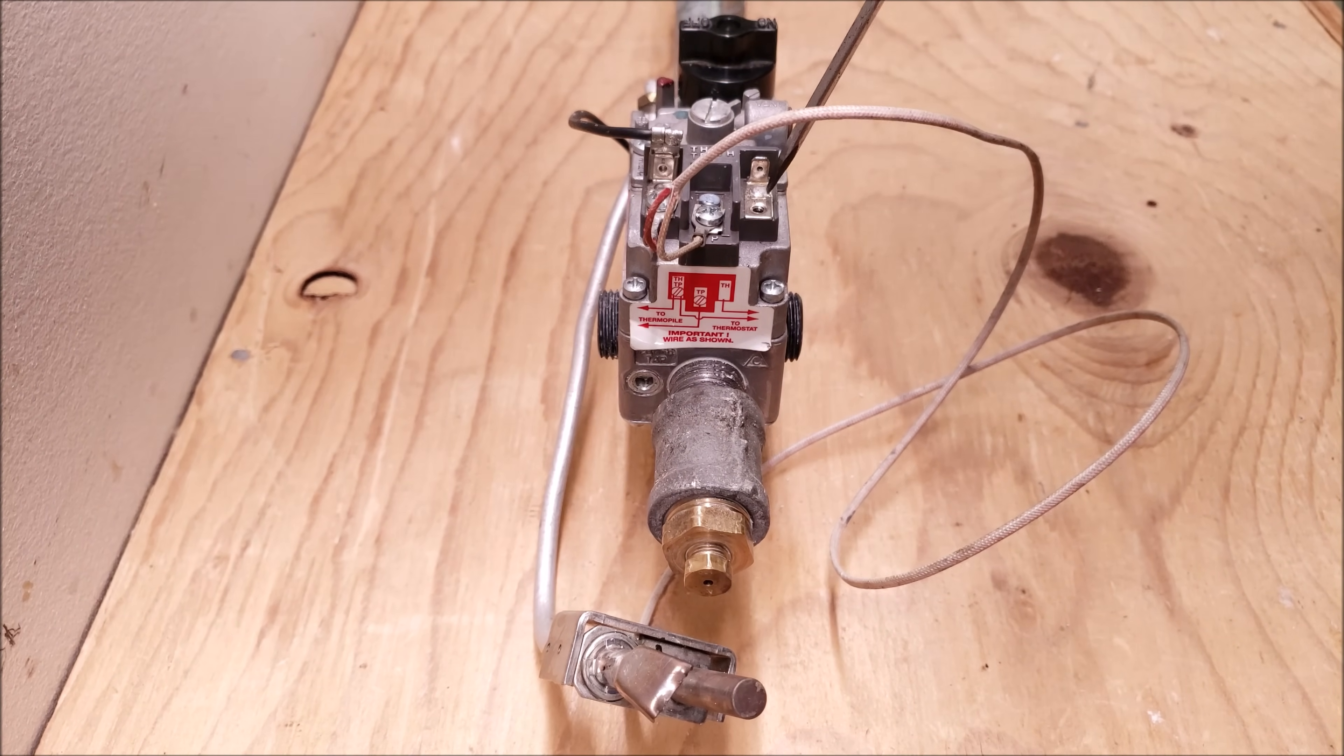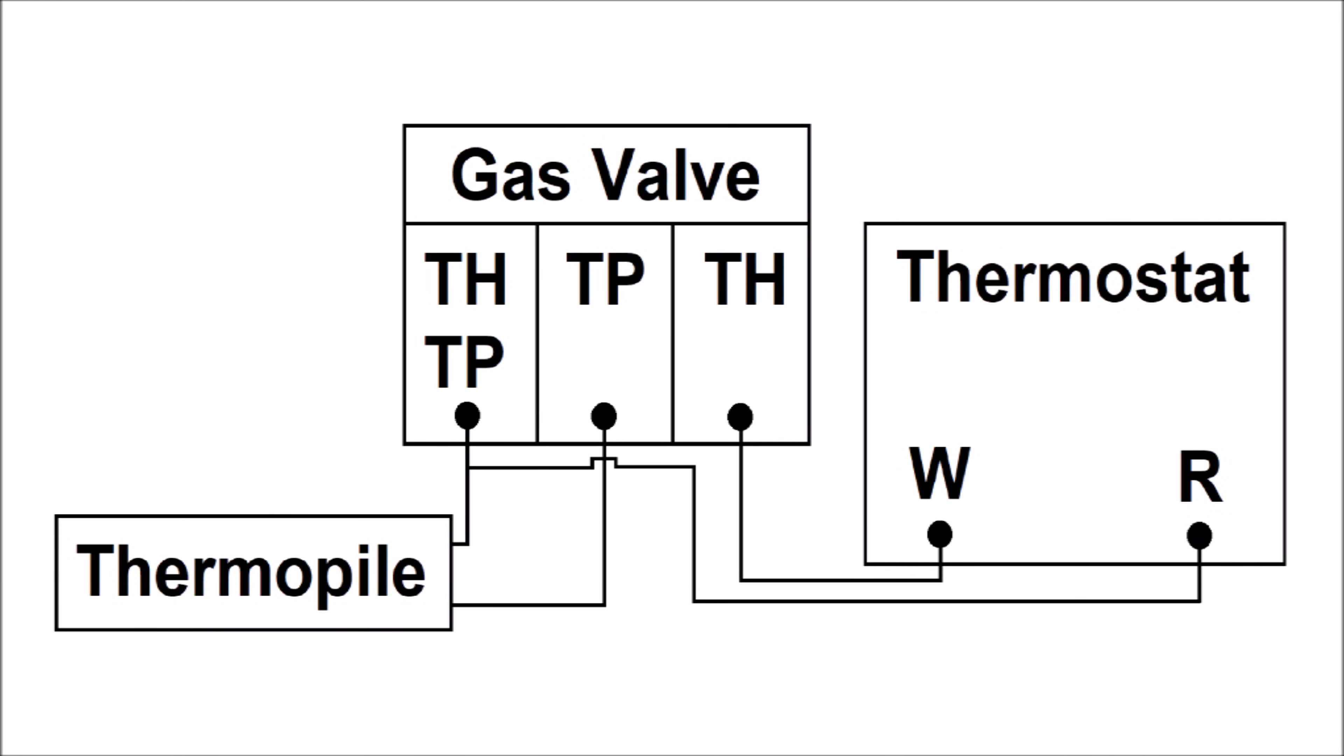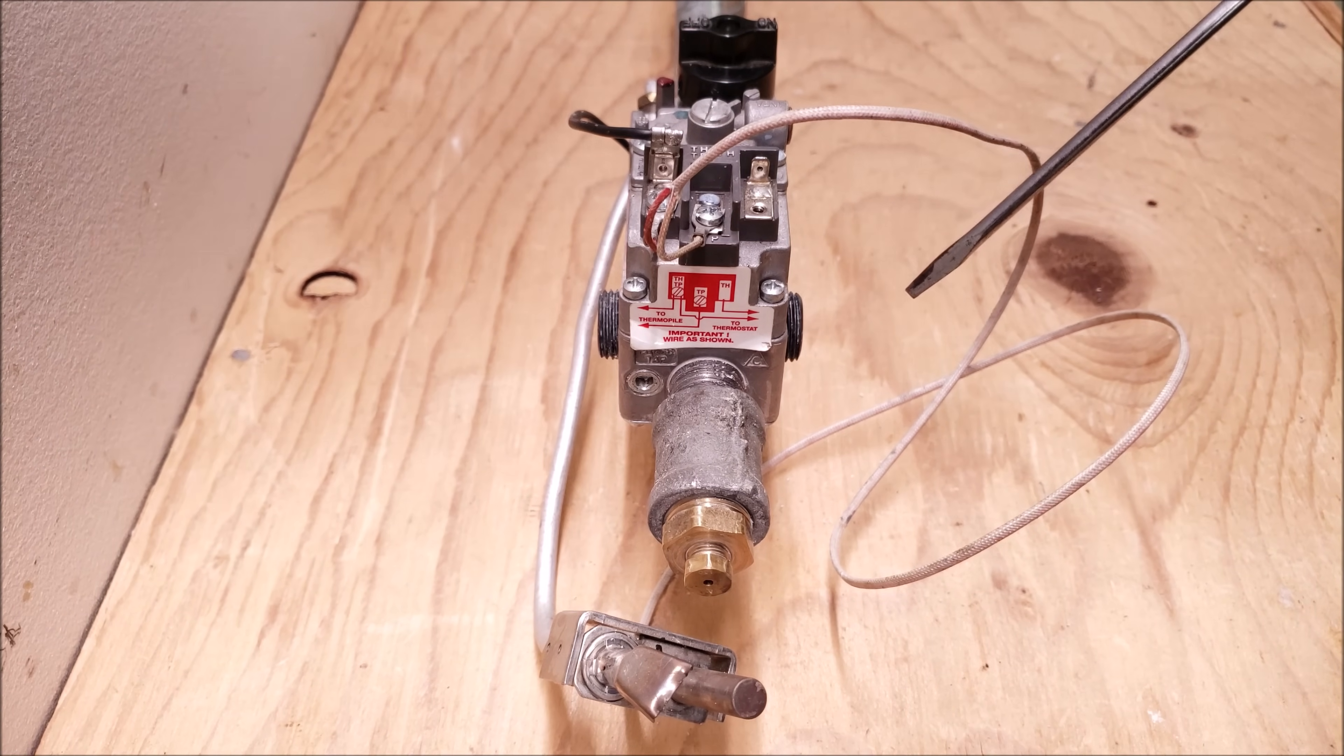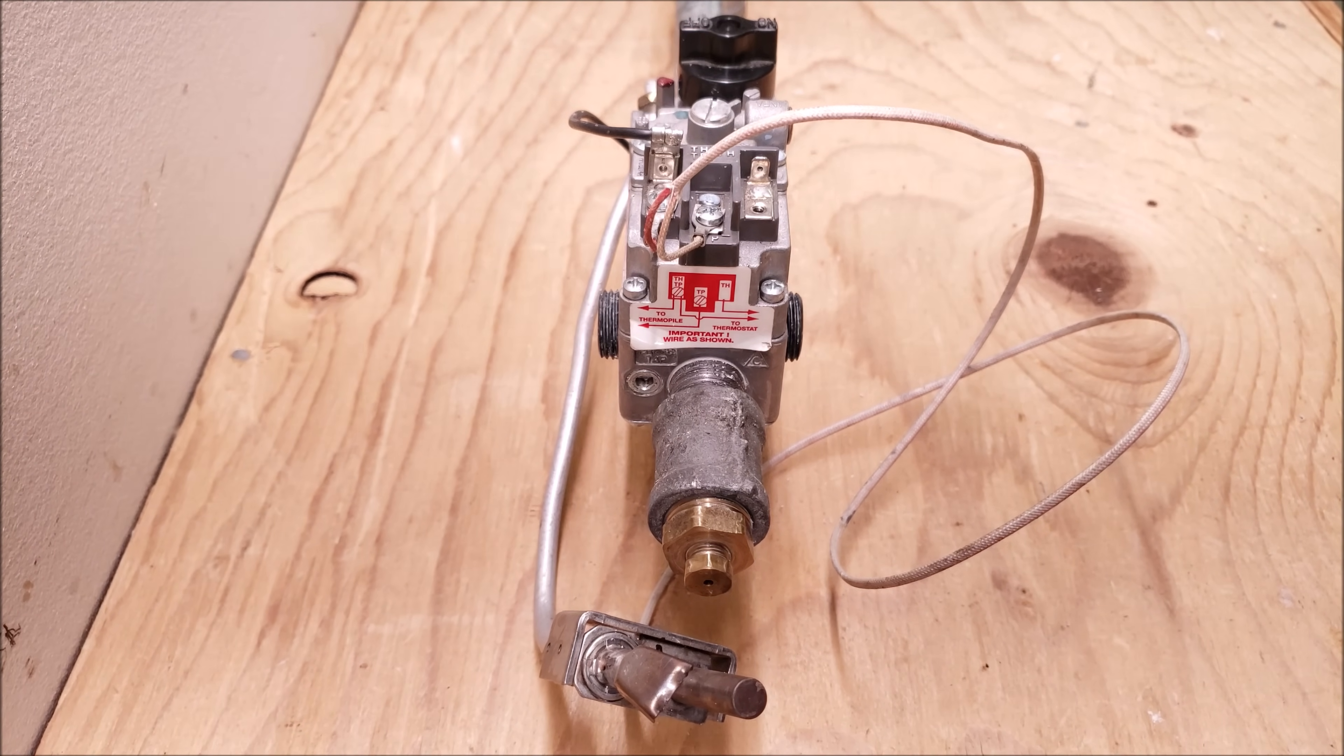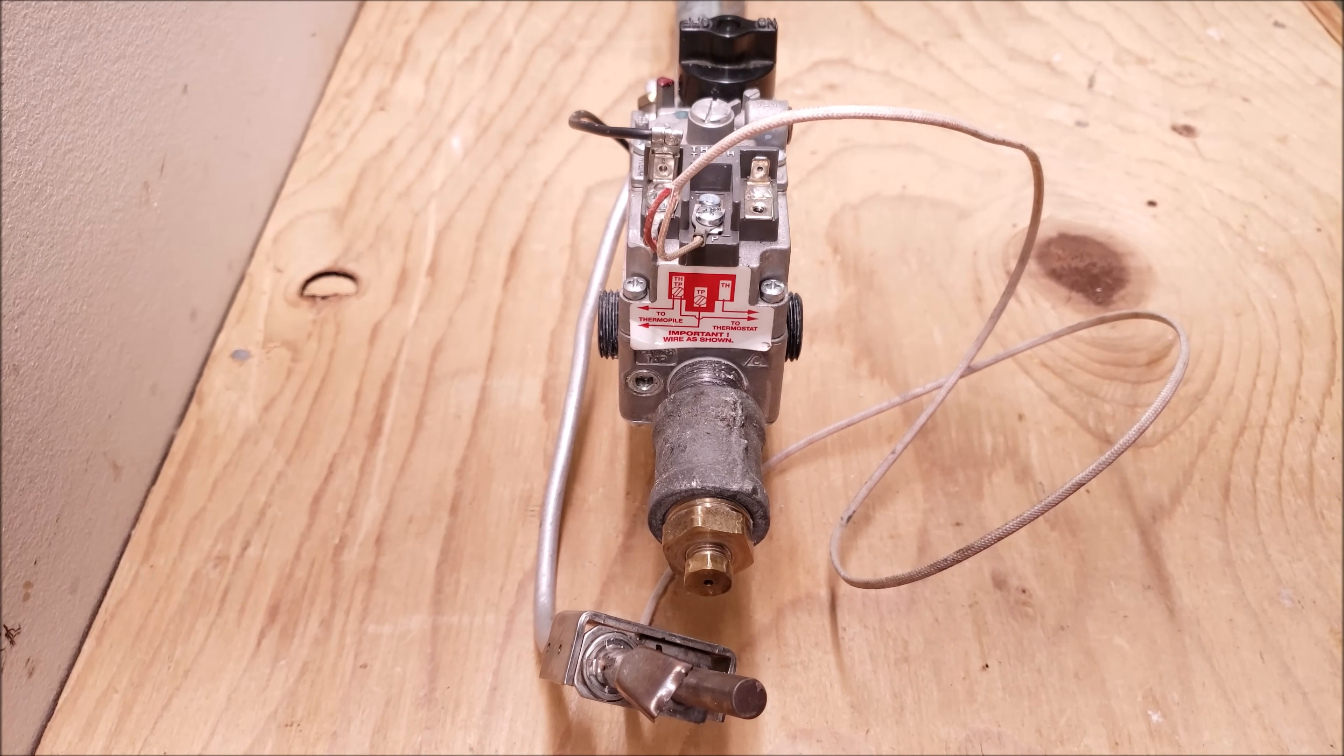It goes through the solenoid and finds its way back through this TP and that's how it powers the main burner. So now I'm going to go ahead and light the pilot so that you can see how this works. If you are looking for a troubleshooting video on the thermopile and millivolt gas valve I have that link down in the description section below.